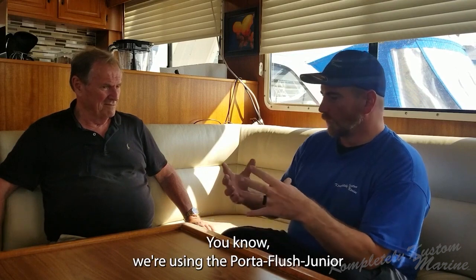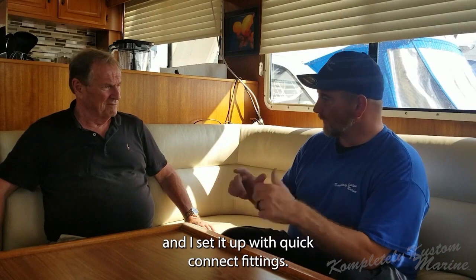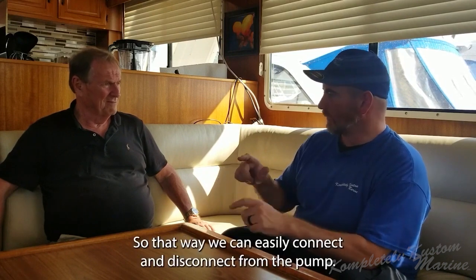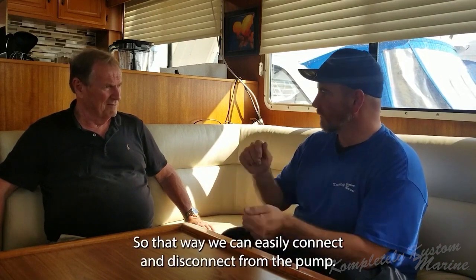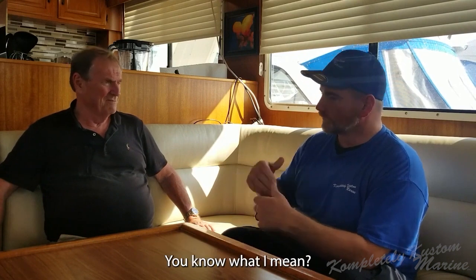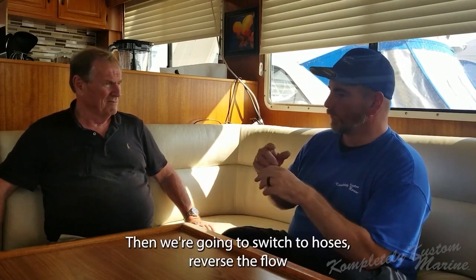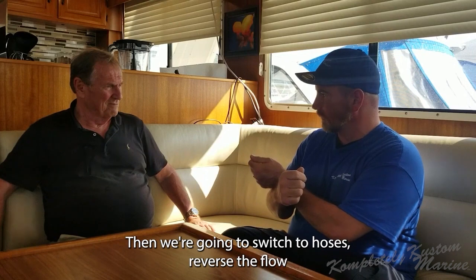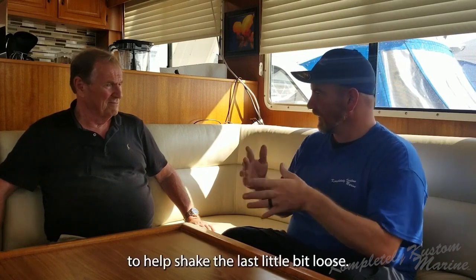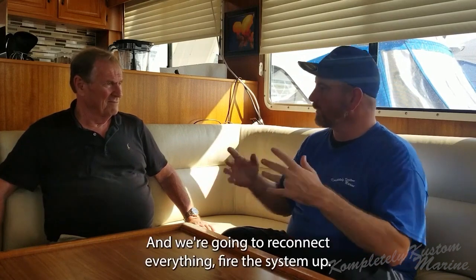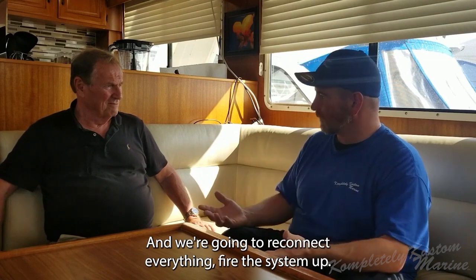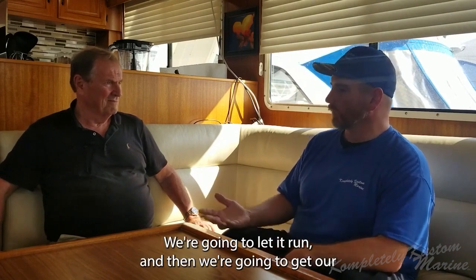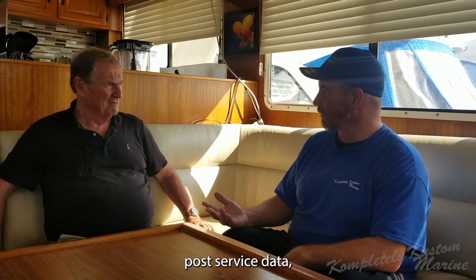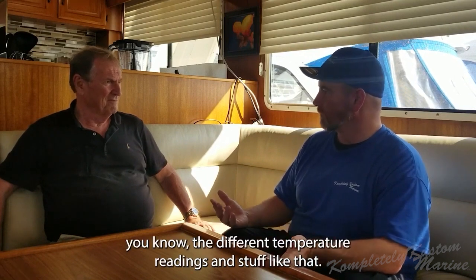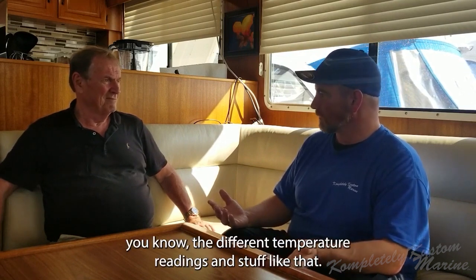We're using the Portaflush Junior, and I set it up with quick connect fittings so we can easily connect and disconnect from the pump. We'll let that run a while, then switch the hoses to reverse the flow and help shake the last bit loose. Then we'll reconnect everything, fire the system up, let it run, and get our post-service data, the different temperature readings and stuff like that.